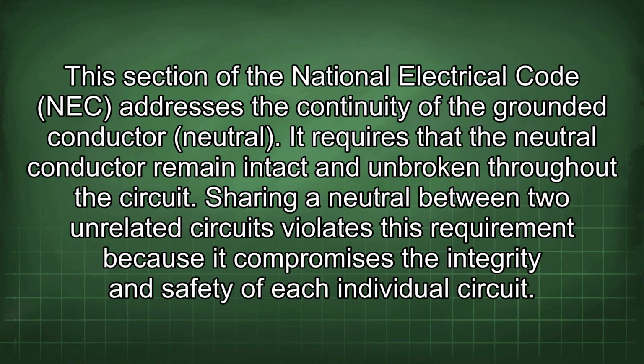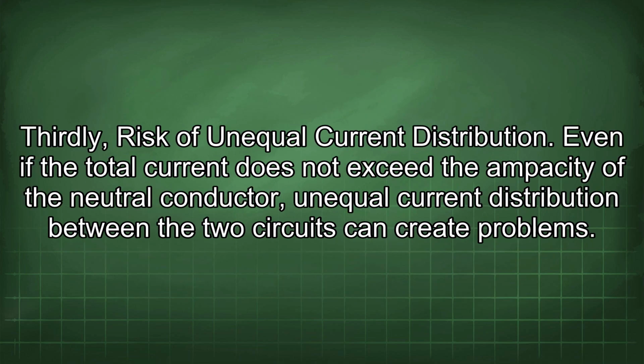Secondly, violation of NEC Section 300.13. This section of the National Electrical Code addresses the continuity of the grounded conductor, the neutral. It requires that the neutral conductor remain intact and unbroken throughout the circuit. Sharing a neutral between two unrelated circuits violates this requirement because it compromises the integrity and safety of each individual circuit.